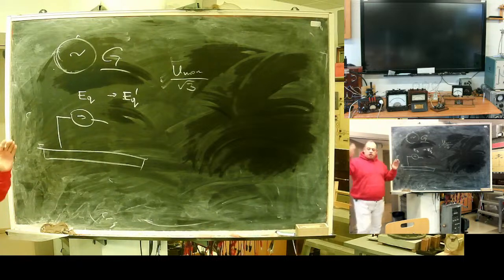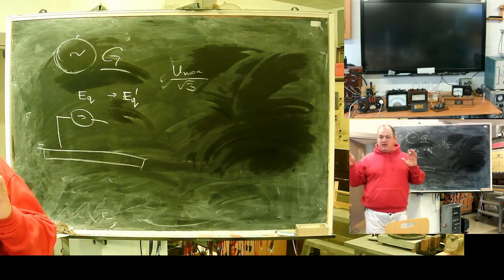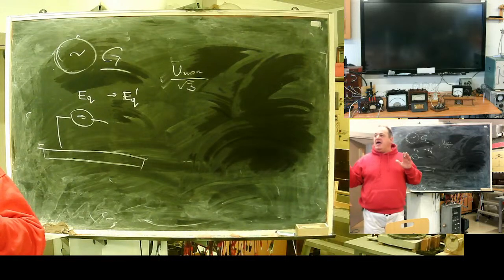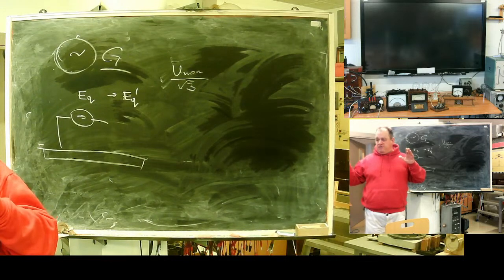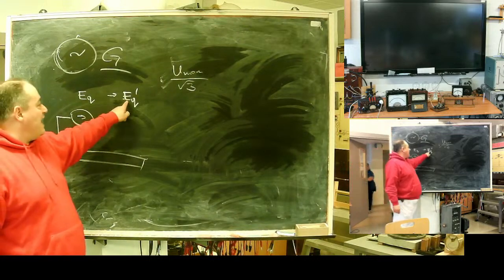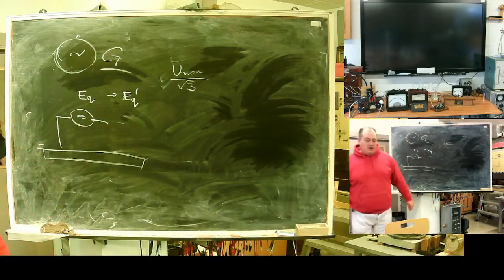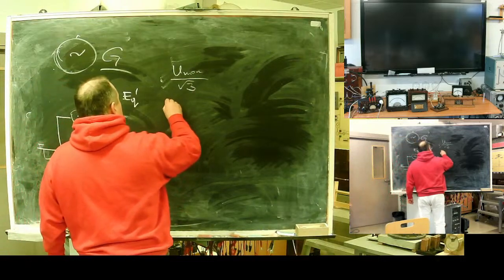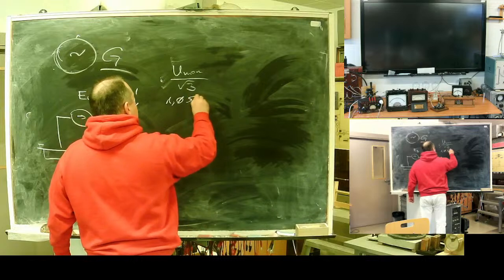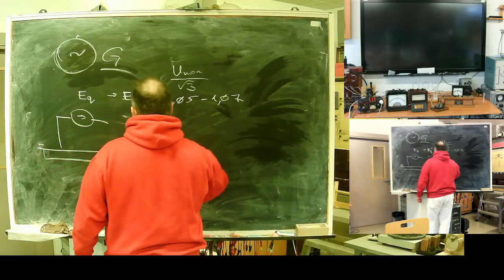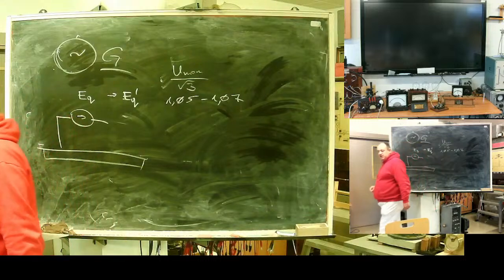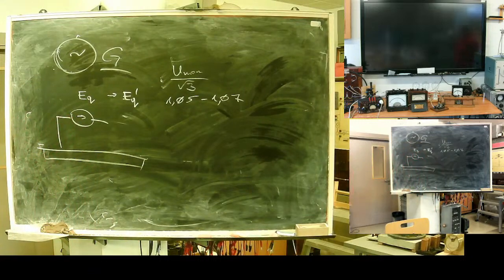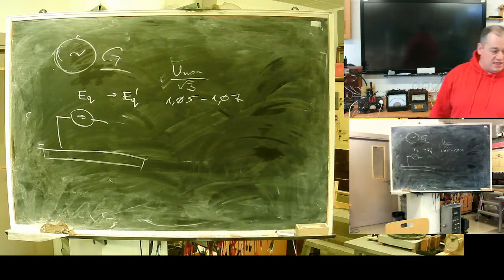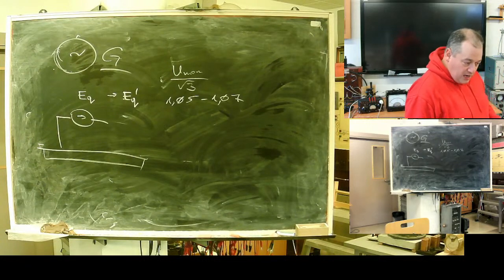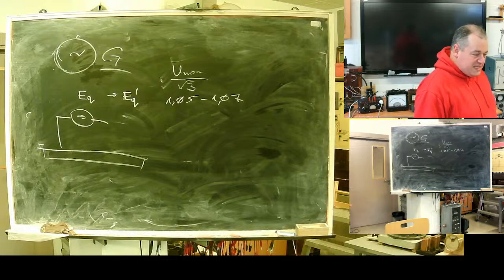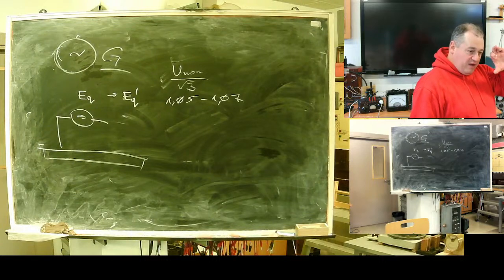The problem is when you short circuit a generator, or make a short circuit somewhere near the generator, the magnetic field energy will give you a transient EMF. It's approximately 1.05, 1.07 of nominal, something like this. It will be greater. This is true for any generator. So for any generator, if you are unlucky and the fault is near the generator, you will see a higher EMF.